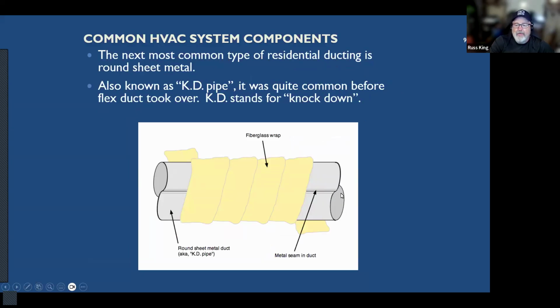Metal duct, okay, straight metal duct. It comes shipped kind of flat, like a U shape, and so they can stack it. All right, they can stack a whole bunch of U-shaped ducts together. But if ducts are round, they can't stack as many of them in a truck. Okay, so they come opened flat like this, and there's a little seam. They bend it over, and there's a little seam that it locks together, and it makes the circular tube. Okay, and so this metal seam, it can leak. It can leak a lot if they don't do a good job sealing it, and so they need to come by and put a bead of mastic, of sealant, on it. And you might hear this called KD pipe, and that stands for knockdown. And all that means is they manufacture it and they flatten it out and they knock it down to flat so that it'll stack.